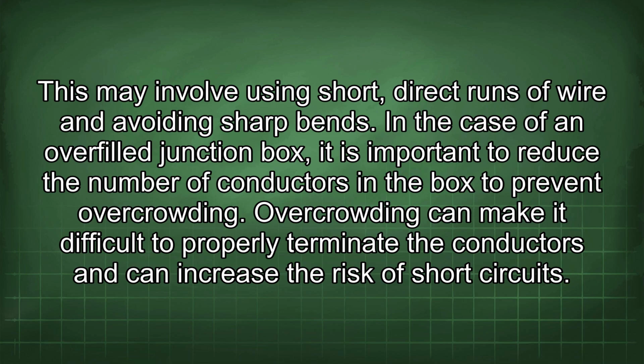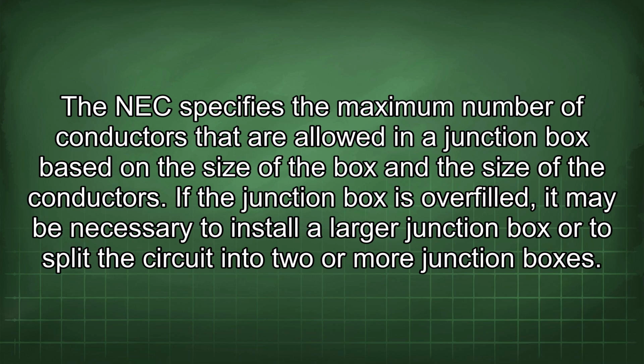In the case of an overfilled junction box, it is important to reduce the number of conductors in the box to prevent overcrowding. Overcrowding can make it difficult to properly terminate the conductors and can increase the risk of short circuits. The NEC specifies the maximum number of conductors that are allowed in a junction box based on the size of the box and the size of the conductors.